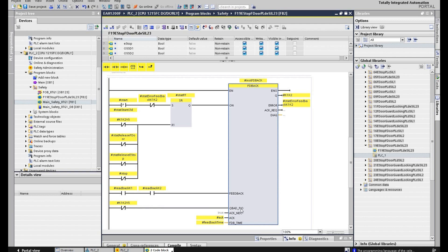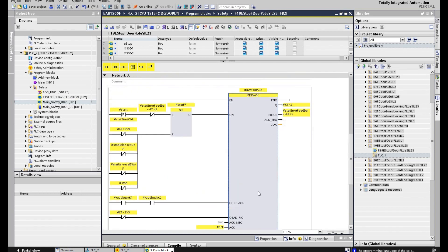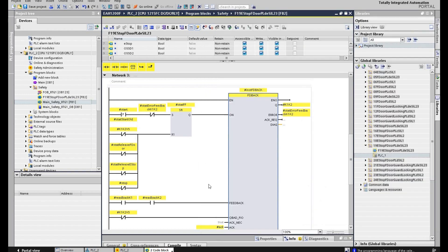That is the output function block. Usually in the Siemens system, to control the output relay we use this feedback function block to connect the output. To implement an emergency stop and safety door without the guarding locking function, especially for this OSSD door switch, that's already enough from this safety program.